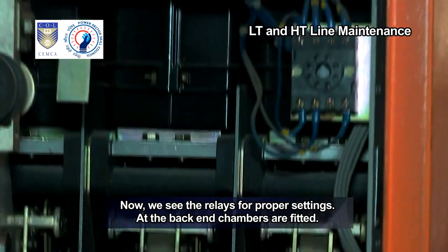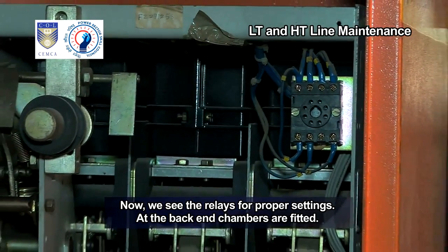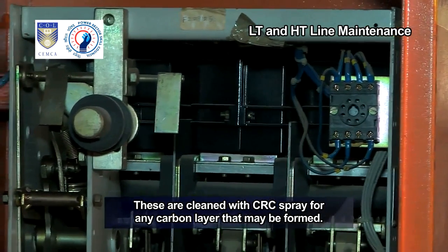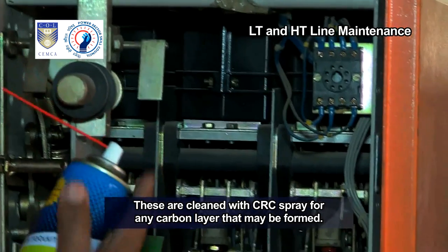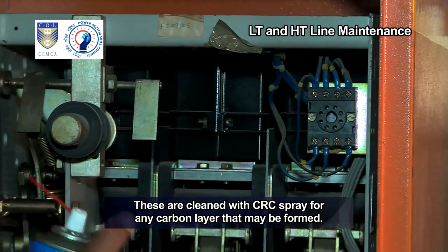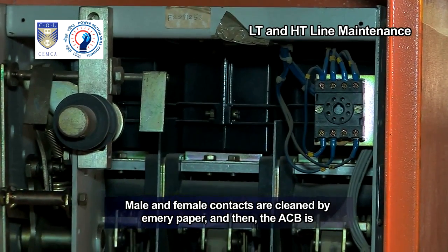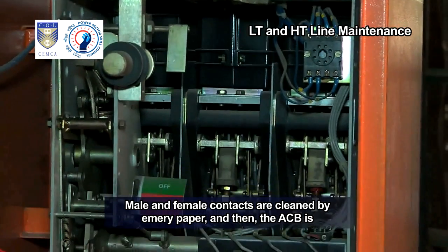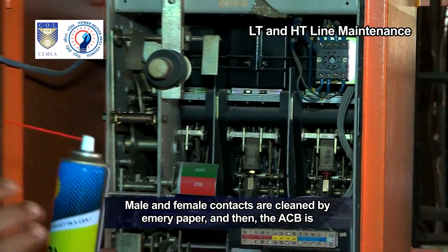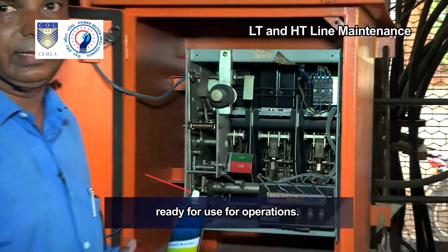Now we see the relays for proper settings at the back-end chambers are fitted. These are cleaned with CRC spray for any carbon layer that may be formed. Male and female contacts are cleaned by emery paper, and then the ACB is ready for use for operations.